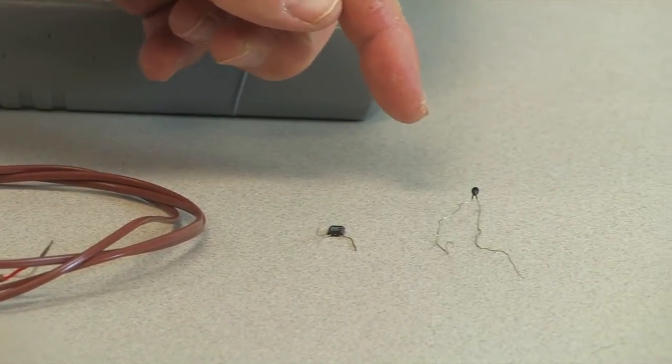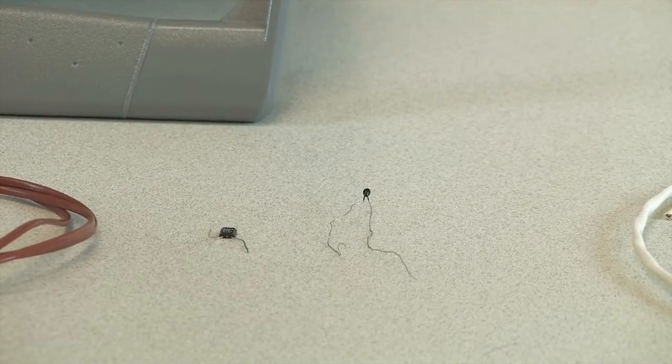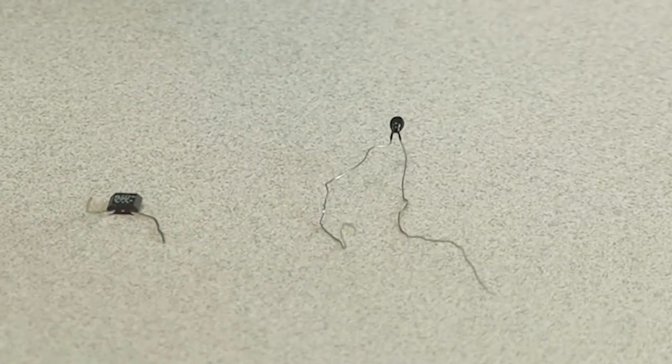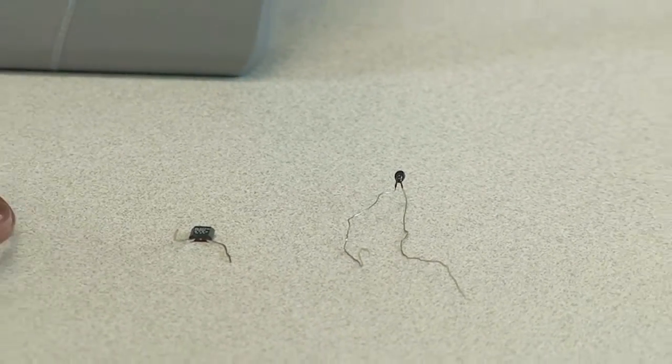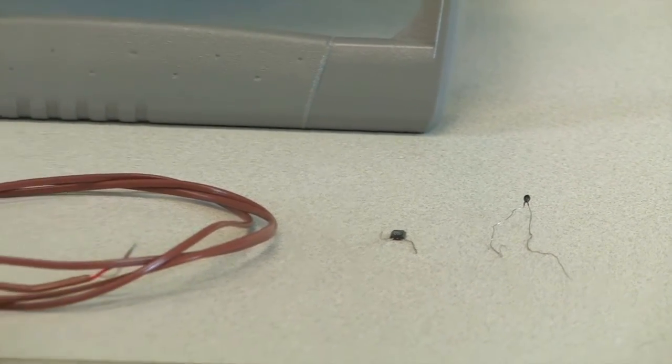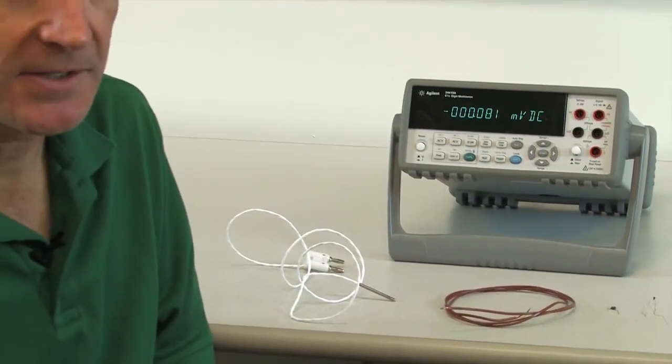A better choice is the RTD or thermistor. Both the RTD and thermistor are resistive devices that change their resistance based on temperature. The RTD is known for being a bit more accurate, it has a larger temperature range, and is a little bit more expensive than the thermistor.